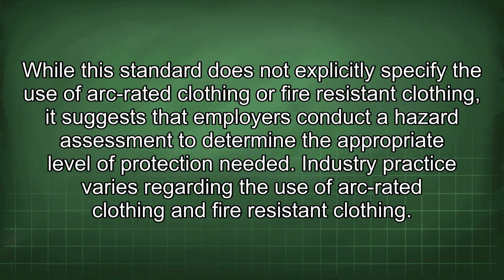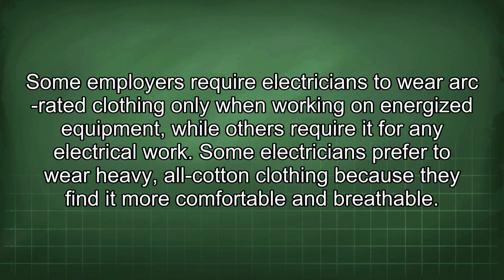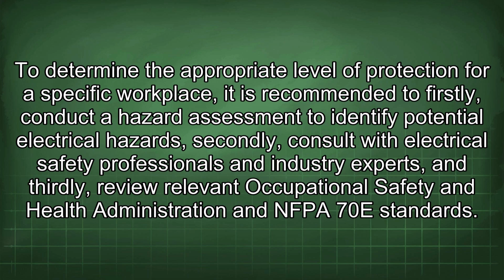Industry practice varies regarding the use of arc-rated clothing and fire-resistant clothing. Some employers require electricians to wear arc-rated clothing only when working on energized equipment, while others require it for any electrical work. Some electricians prefer to wear heavy, all-cotton clothing because they find it more comfortable and breathable. To determine the appropriate level of protection for a specific workplace, it is recommended to firstly conduct a hazard assessment to identify potential electrical hazards, secondly consult with electrical safety professionals and industry experts, and thirdly review relevant Occupational Safety and Health Administration and NFPA 70E standards.